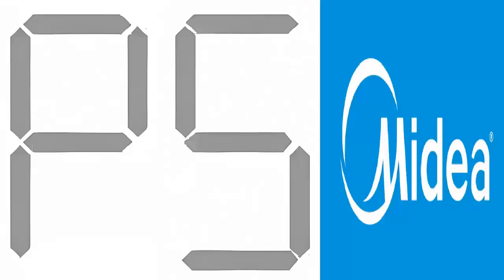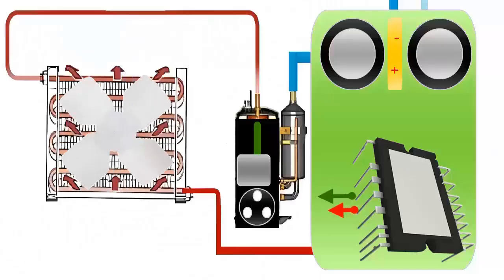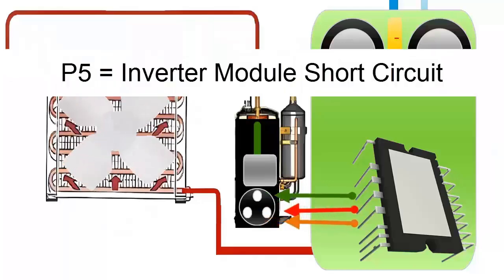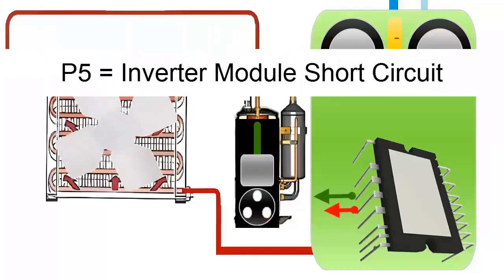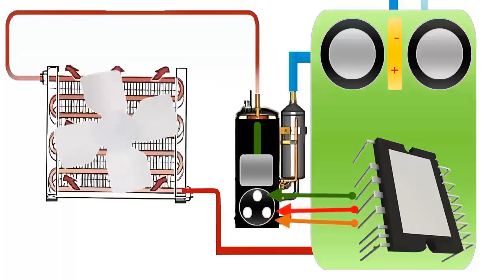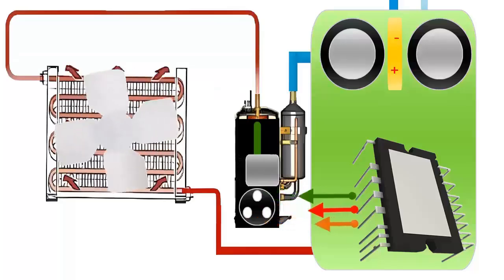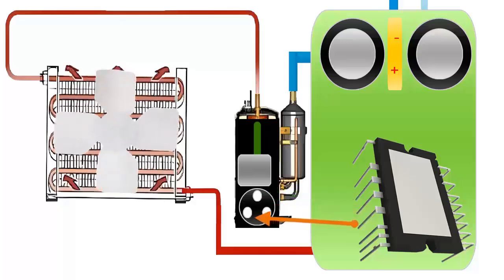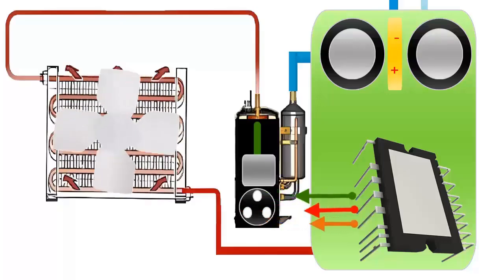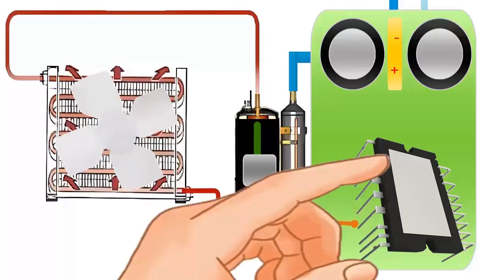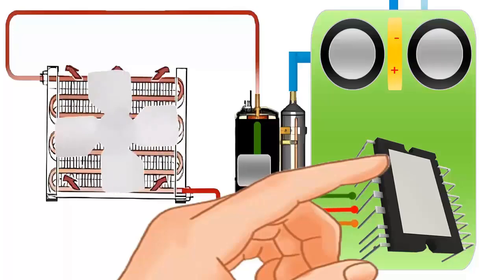Code P5 generally indicates inverter module protection, likely due to overheating or an internal short circuit in the inverter module. Recommendations: A. Check the electrical connections powering the compressor. B. Test the power module to the compressor, as we will show at the end of the video.